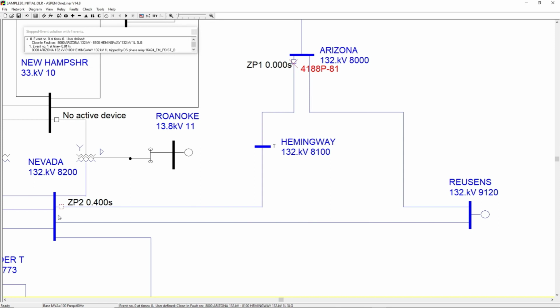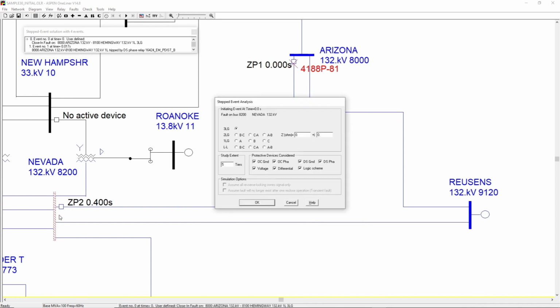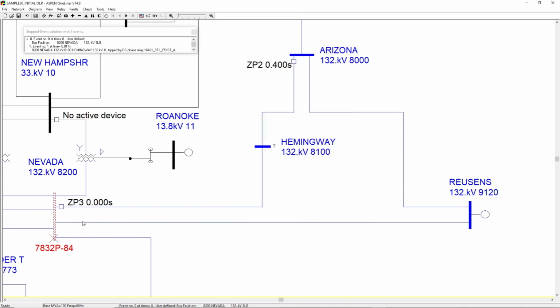They would also need to know what elements are tripping for each relay in order to represent protection accurately. After all, a zone 3 reverse element used for DCB blocking should not trip, unlike the case we see here. Improper modeling of relay functions can have rather unfortunate effects on protection performance studies.